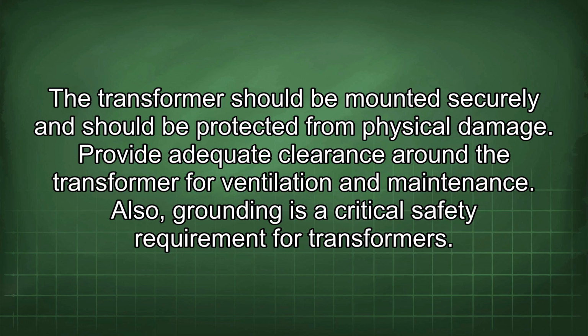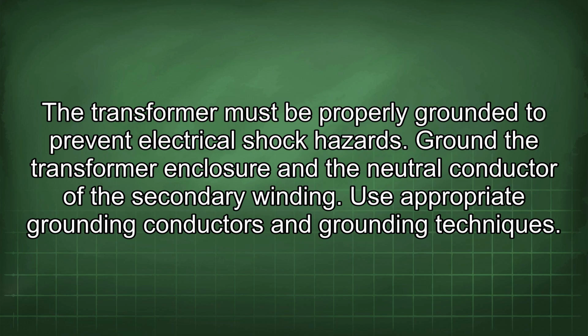Also, grounding is a critical safety requirement for transformers. The transformer must be properly grounded to prevent electrical shock hazards. Ground the transformer enclosure and the neutral conductor of the secondary winding. Use appropriate grounding conductors and grounding techniques.